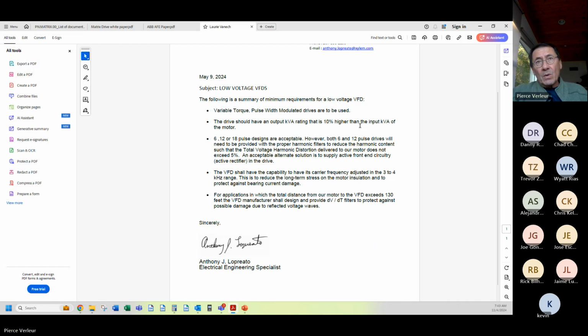Why? Well, the motor will be rewound 2 to 3 times during the lifetime of the drive. Each time the motor is rewound, it loses a bit of its efficiency no matter how good the rewind is. And that loss of efficiency is about 2 to 3%. So by the time you get to the third rewind, you're at 10%, and you don't want your drive to be undersized during the lifetime of the motor. So just for that reason alone, and there are other ones, this is a good reason to have this service factor of the VFD on the motor. I'm going to skip this and come back to it.